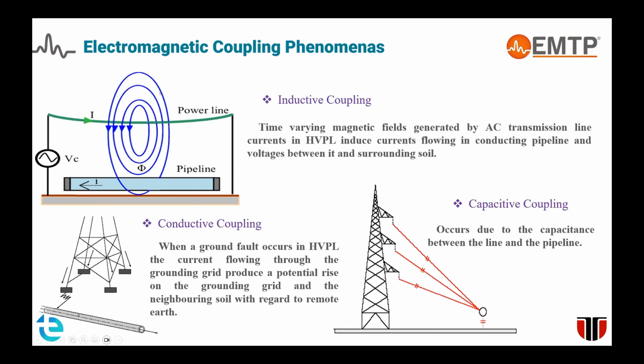But this conductive coupling could happen only in this kind of lightning faults, or let's say if we have a phase to ground fault, when one of the phase wires due to a storm is broken and falls to the ground and it's close to the pipeline.